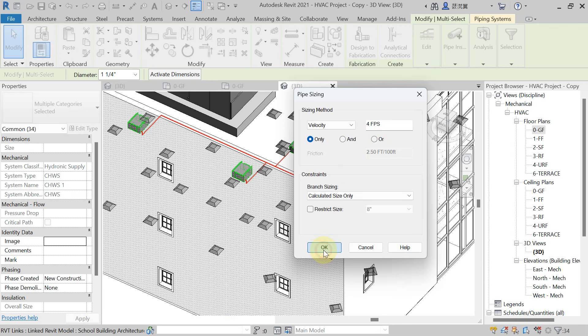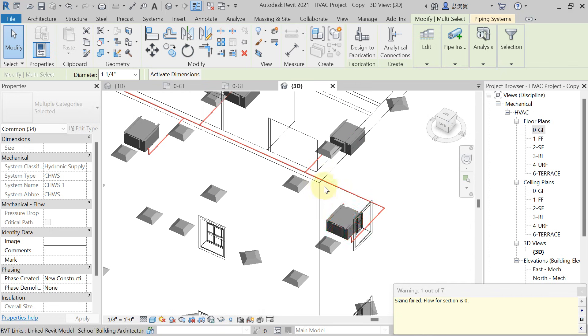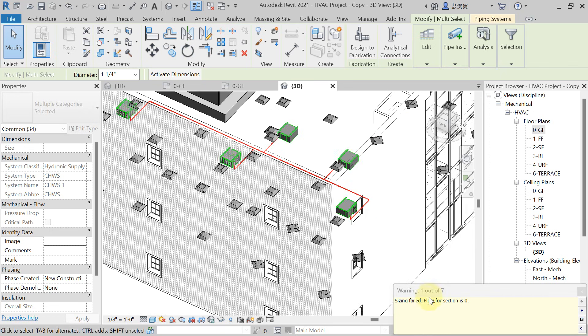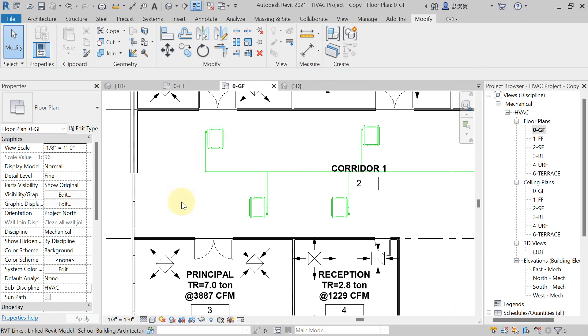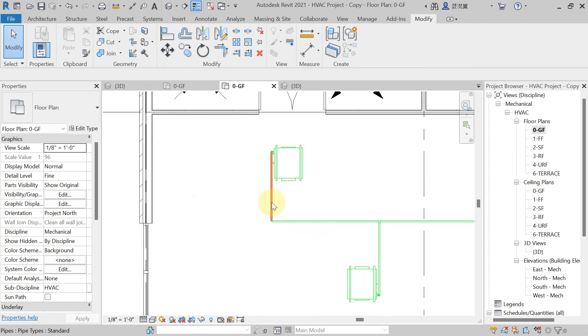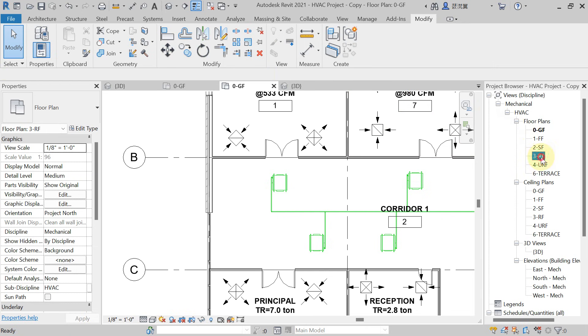Hit on OK. It is showing sizing fail — the flow for the section is zero. Why? Because we have not connected this pipe to the chiller, that is why the sizing is showing fail. First, you have to size the pipe up and connect it to the chiller.